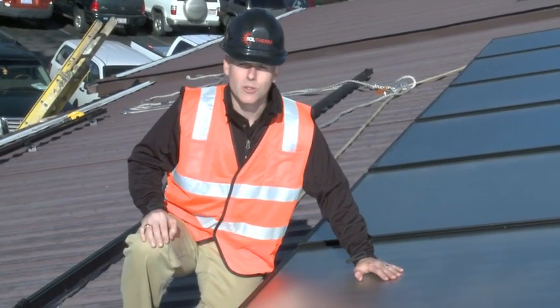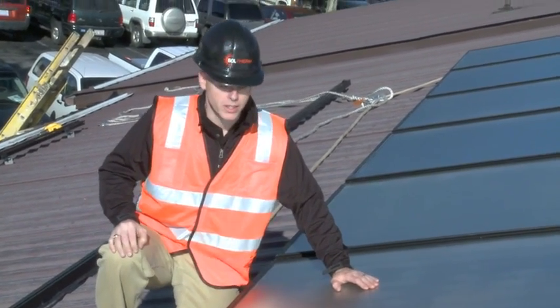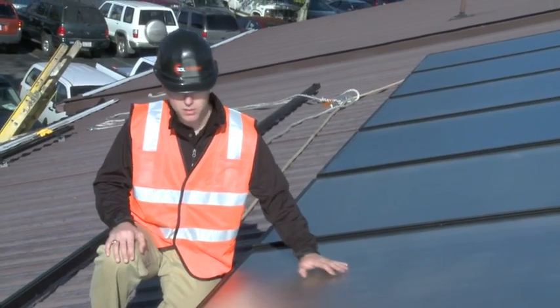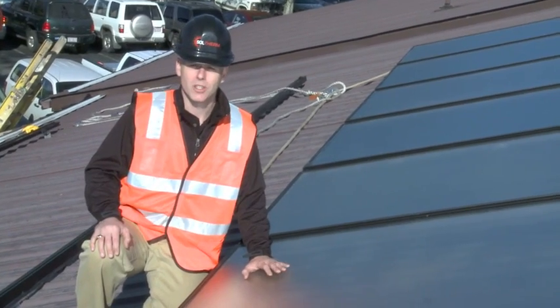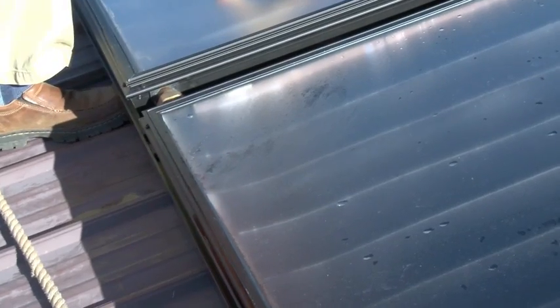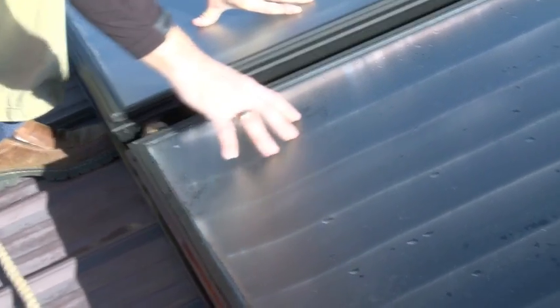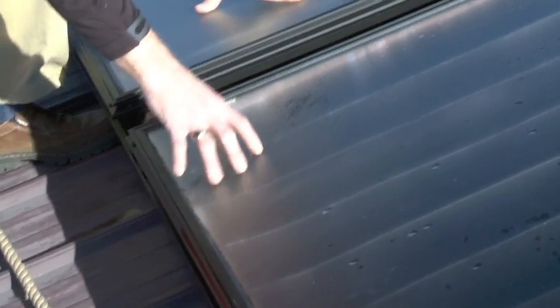What we have here is a solar thermal flat plate collector by Heliodyne, manufactured in the United States. The construction of this technology has not changed that much in the last hundred years. In a flat plate collector there are a few basic components that enable the transfer of energy. You have the glazing, which is a tempered glass that is textured so it prevents reflection of solar rays — it's designed to collect as much radiation as possible.